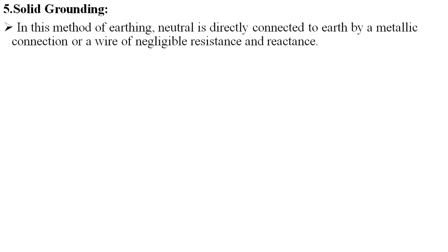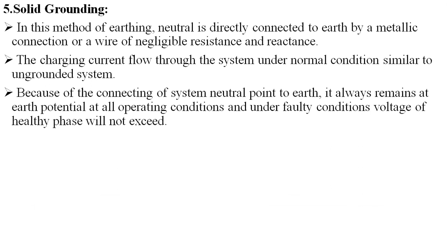Solid grounding. In this method of earthing, neutral is directly connected to earth by a metallic connection or a wire of negligible resistance and reactance. And the charging current flows through the system under normal conditions, similar to an ungrounded system. Because of the connection of the system neutral point to earth, it always remains at earth potential at all operating conditions, and under faulty conditions, the voltage of the healthy phases will not exceed the normal value.